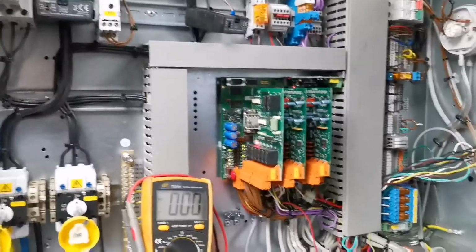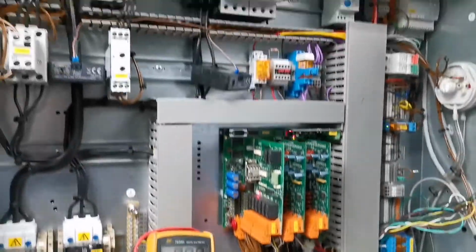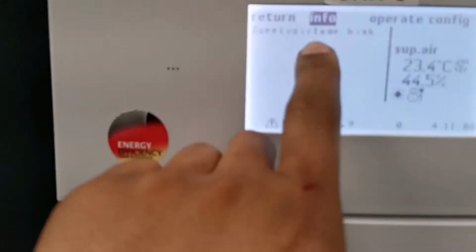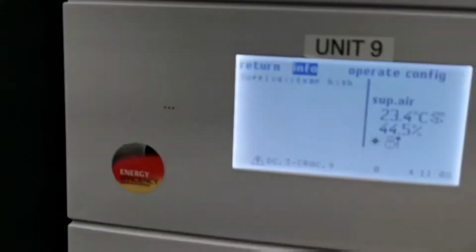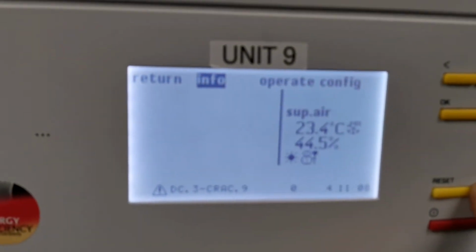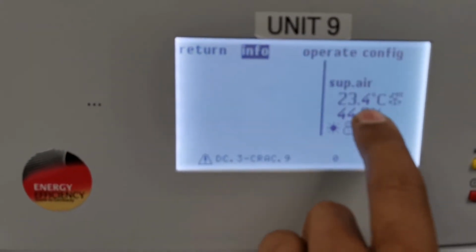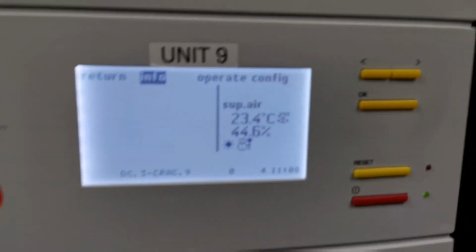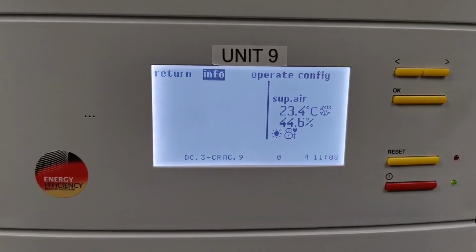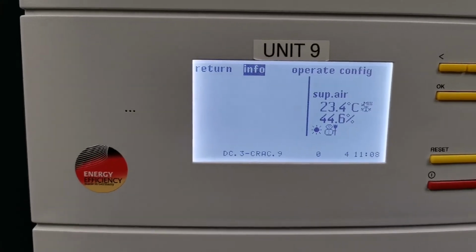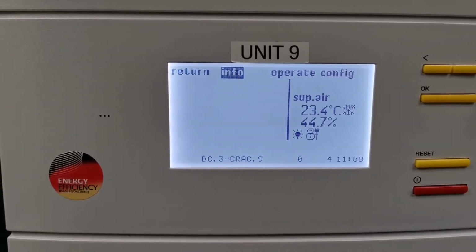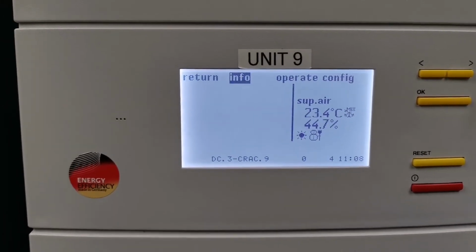There we go. So is this one of those moments where one needs to make an educated guess? Let me know in the comments, guys. So we just got a high temperature alarm, but that's fine because the alarm set point is set to 23.5. We were slightly above that, that's why we got an alarm over there, but everything seems to be running fine, which is quite weird.